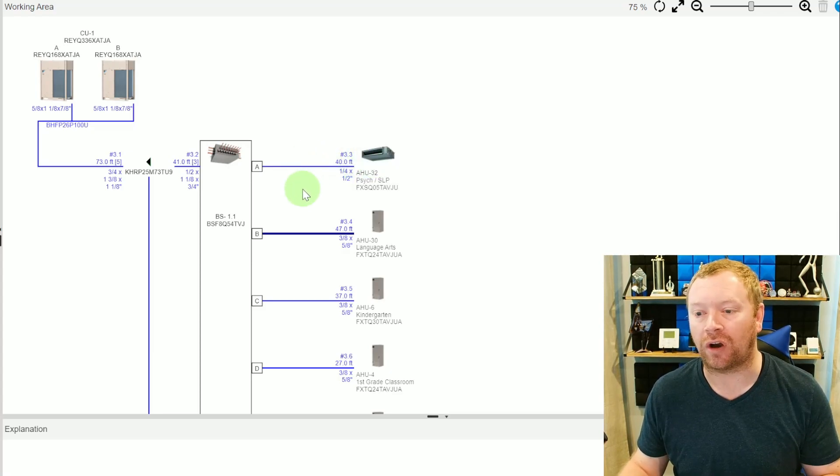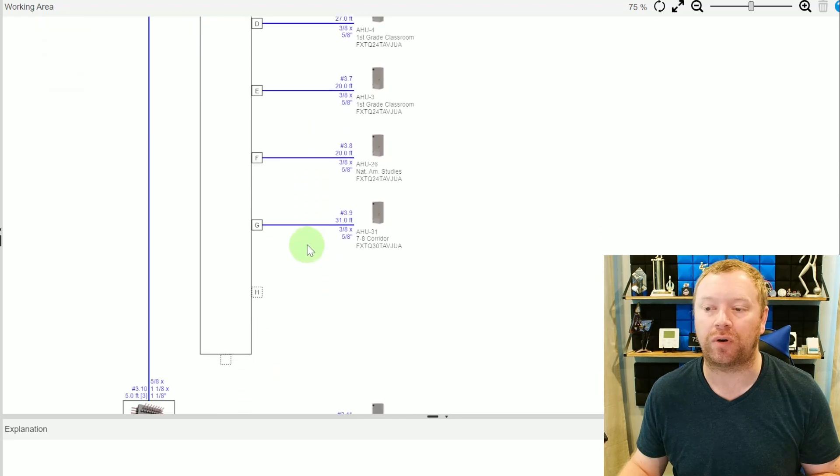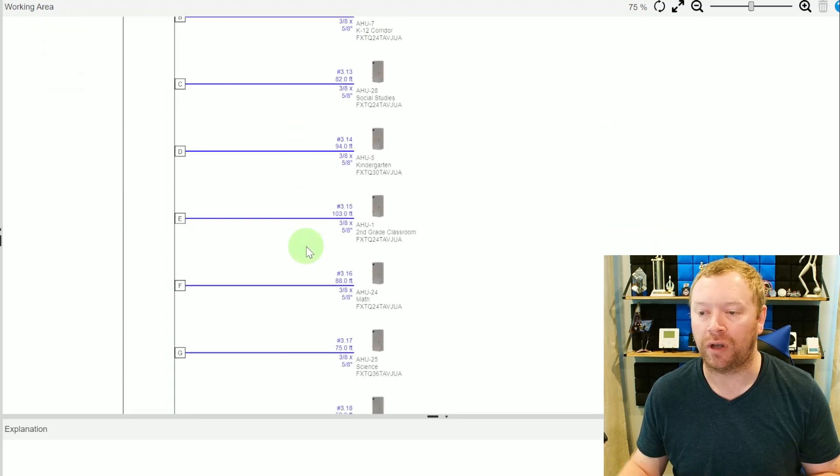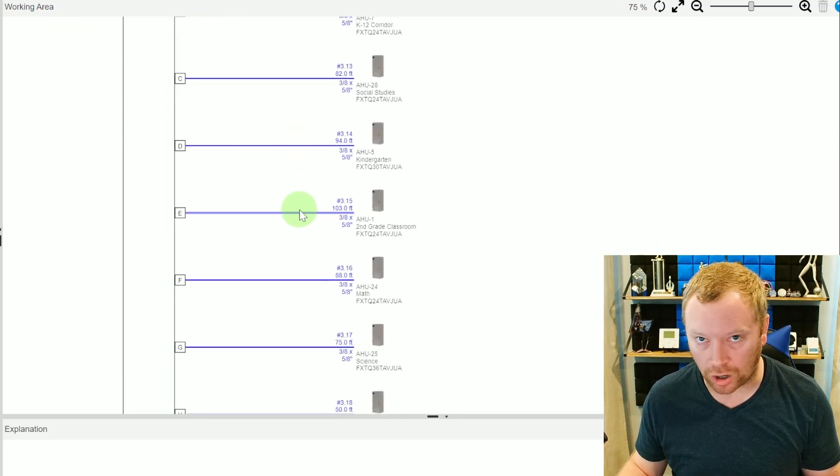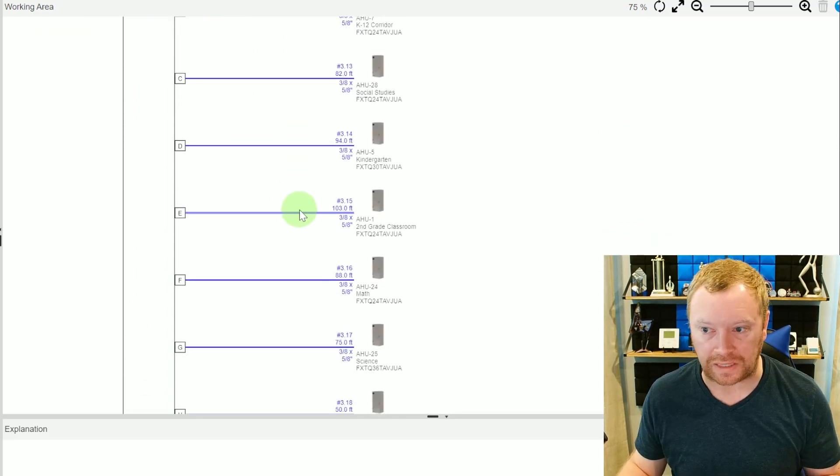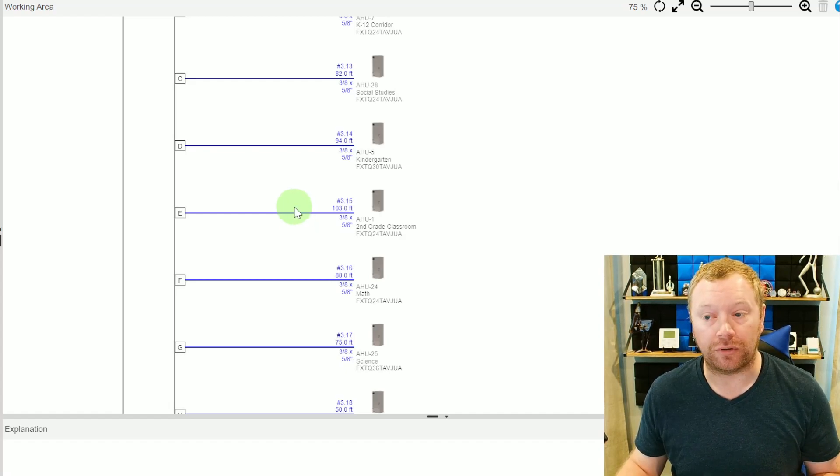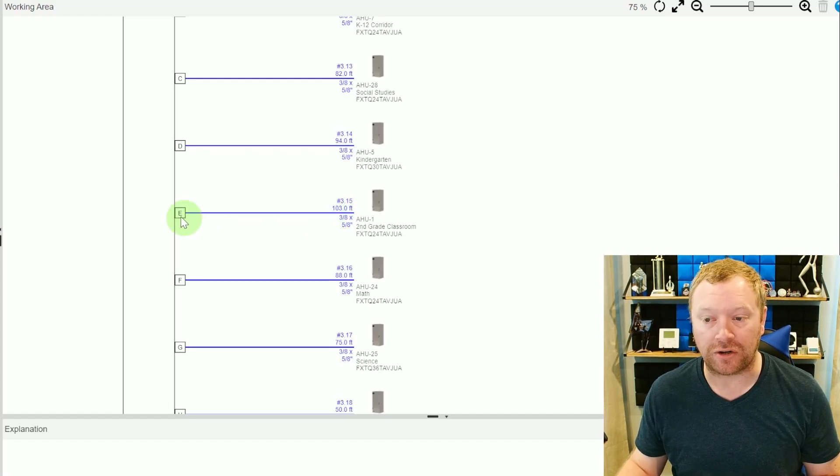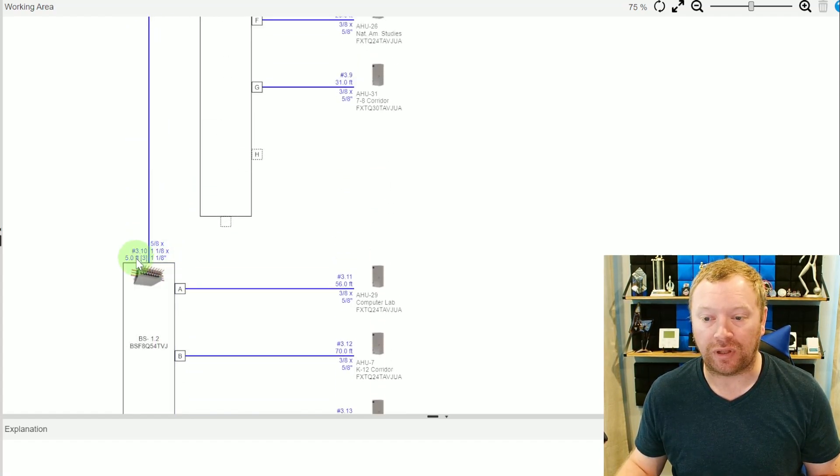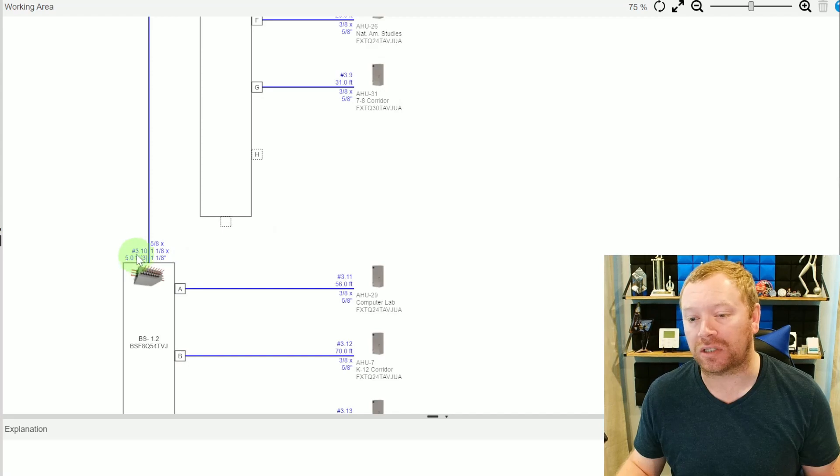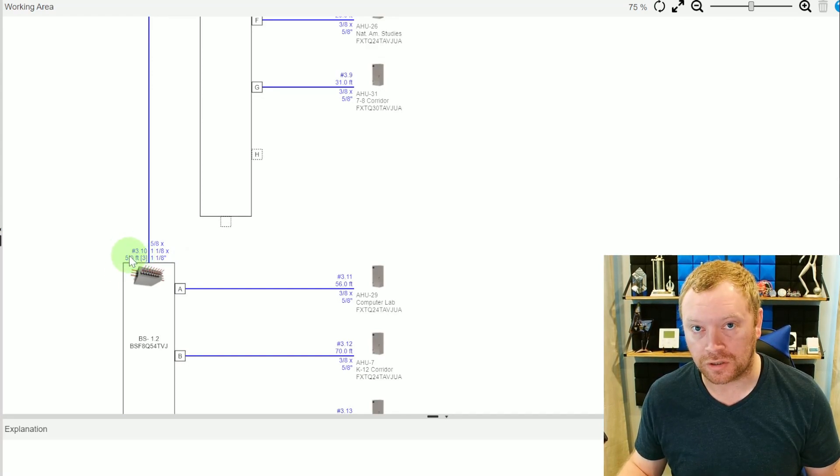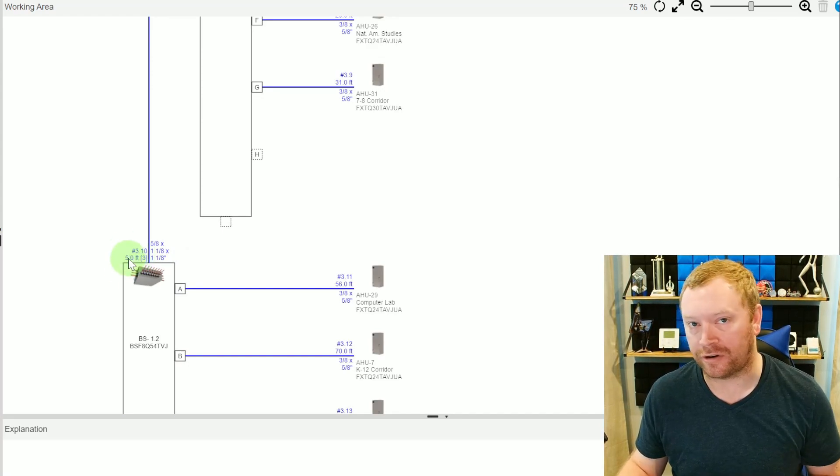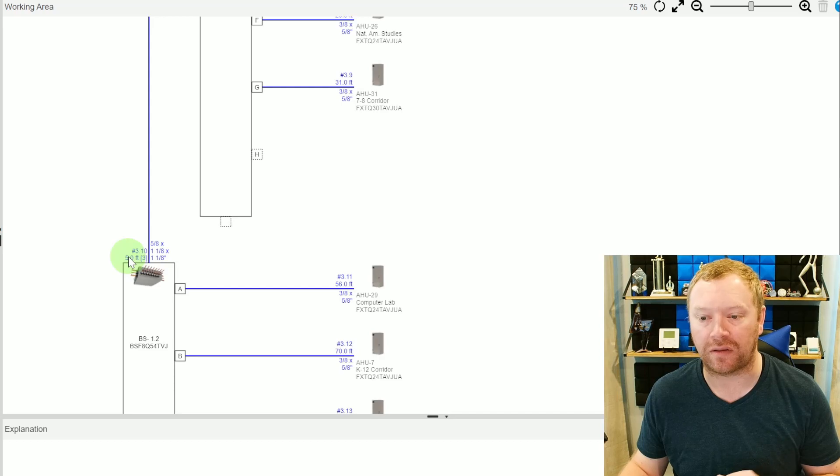As you're running all of these units and you come across one and go, oh man, this one down here is 103 feet. I should probably do a check. Let's go measure that. 103 feet plus, oh, this box is only five feet away from the branch. So we're only at 108 feet. So we're fine there.